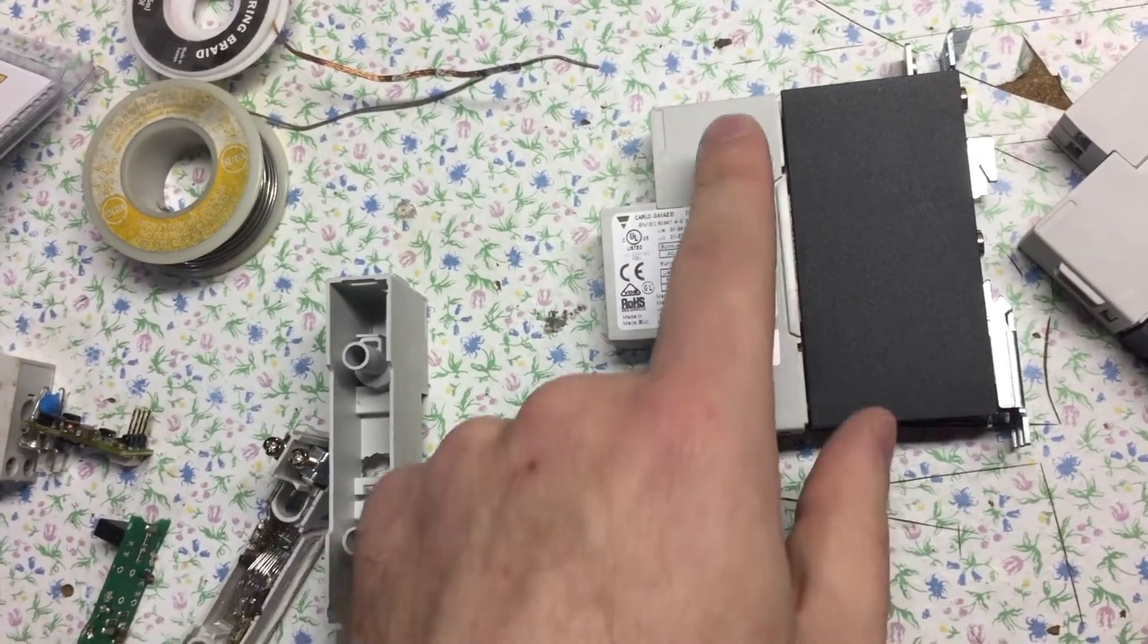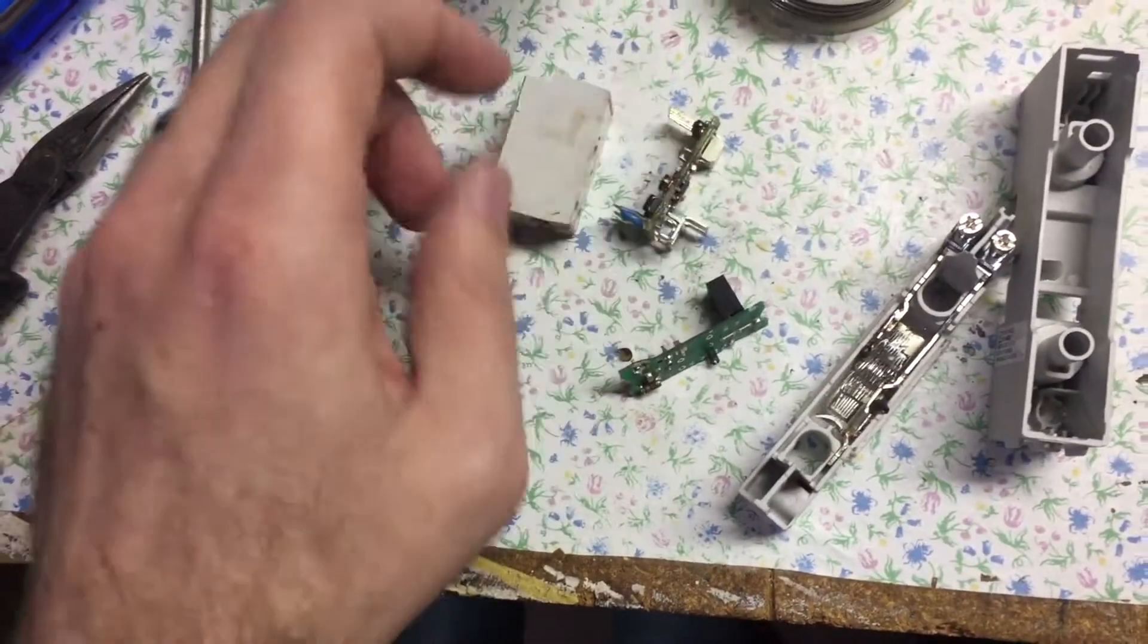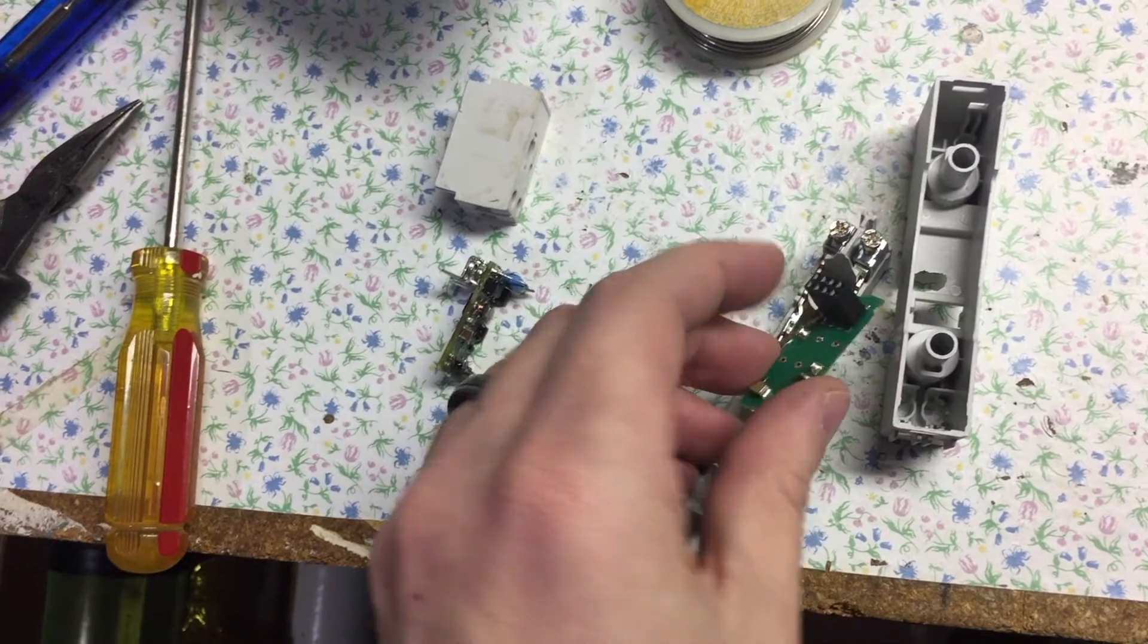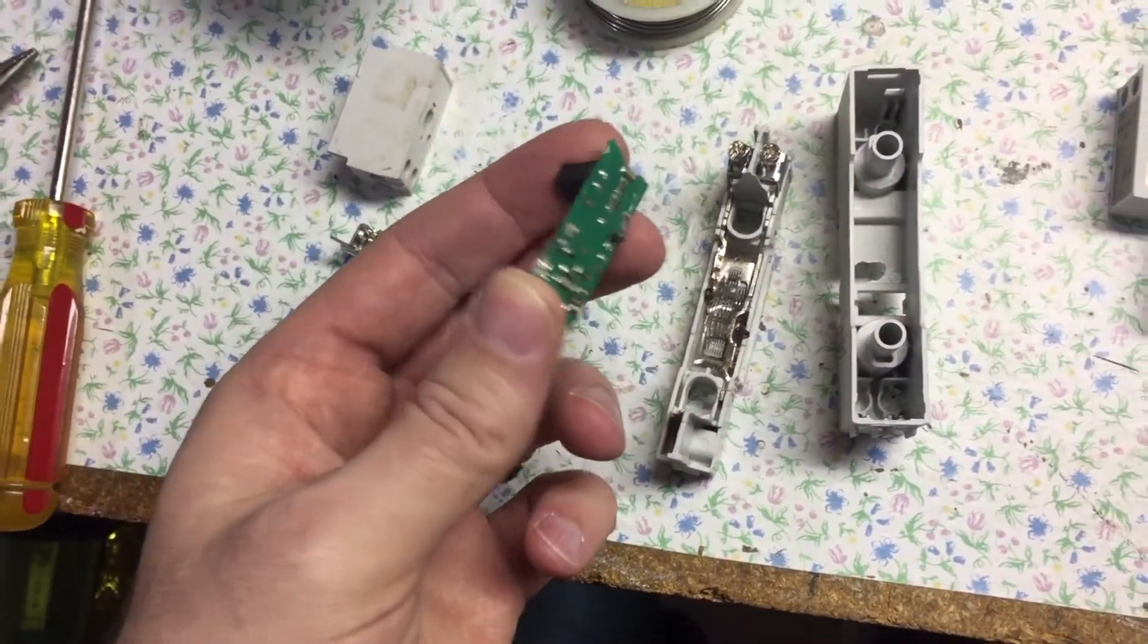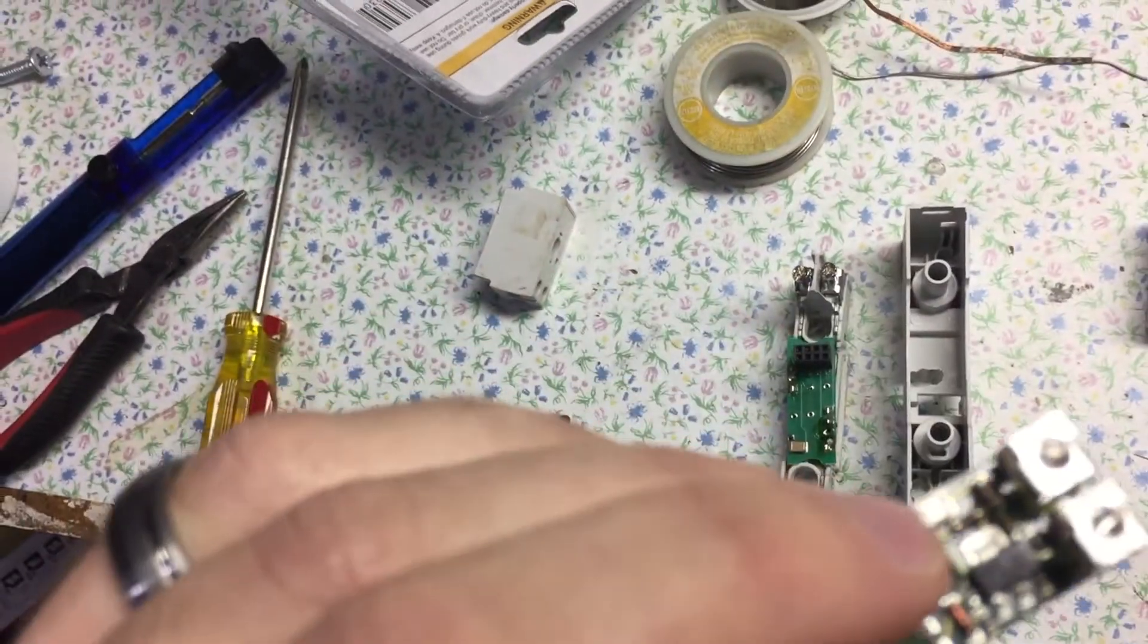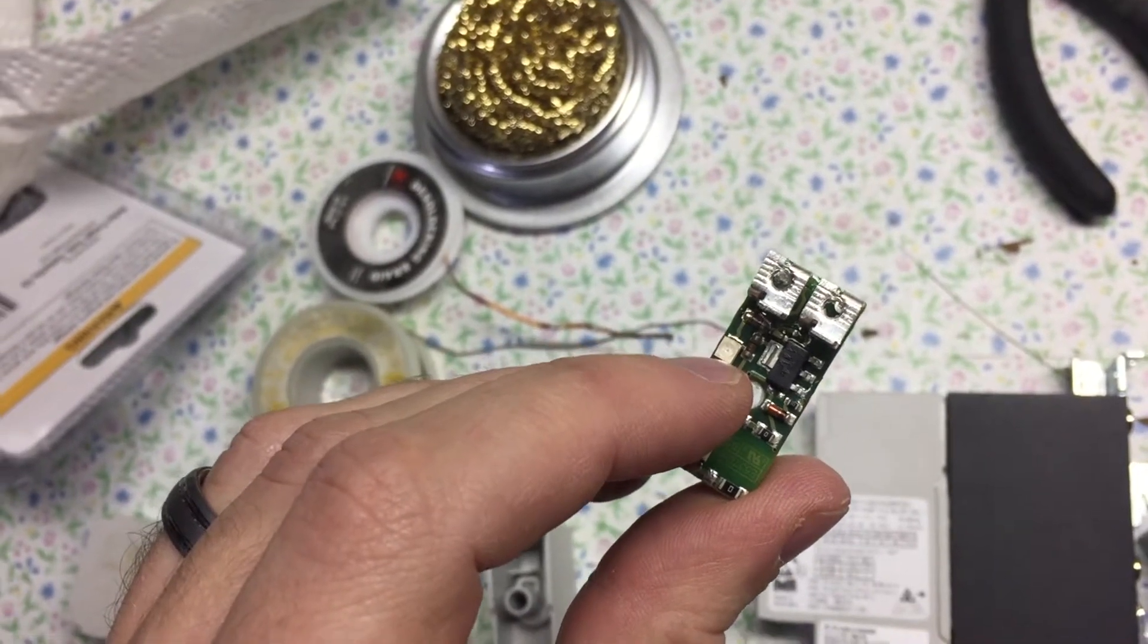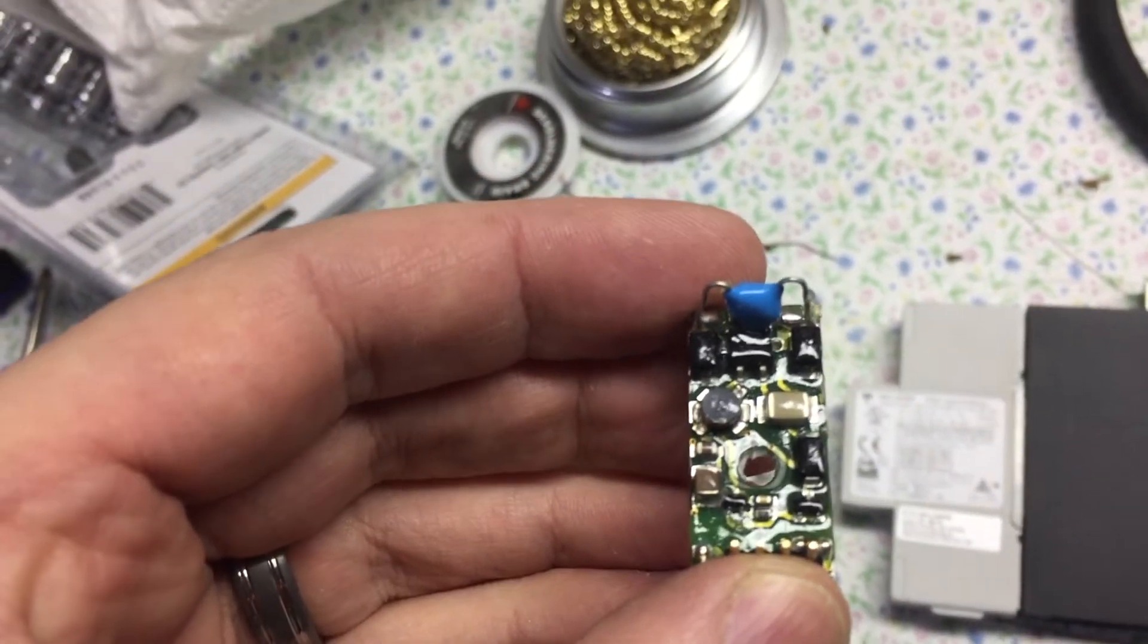The way it comes apart is this is a big heat sink on the back, and then in here is the actual high power high voltage side. Up here is the low voltage from the PLC that comes into a little board. There's pins that go through to connect to this board which is then normally attached in here - I've cut it and desoldered some of it to get it off. Because that light isn't coming on, we know this part is most likely not the issue because that's the high voltage side. We know it's going to be on the low voltage side because the light should be coming on. They mentioned the optocoupler was bad in these, and the optocoupler is actually that little square thing in the middle there - you can see the two pins right underneath that capacitor, that blue capacitor.